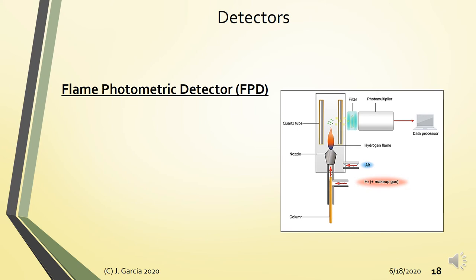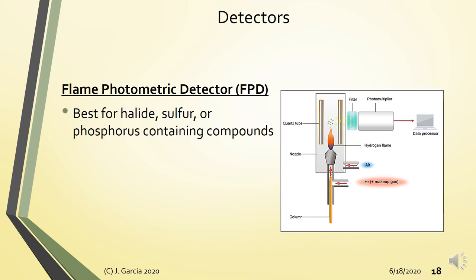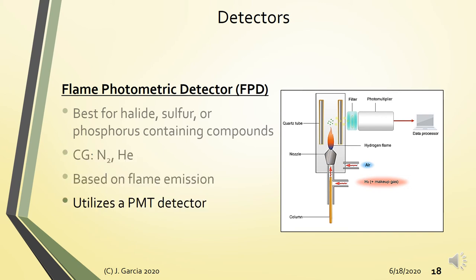The flame photometric detector (FPD) is used for halide-, sulfur-, or phosphorus-containing compounds. It is based on light emission: compounds containing halide, sulfur, or phosphorus emit characteristic emissions during combustion. Common carrier gases are nitrogen and helium. It utilizes a photomultiplier tube and is quite sensitive as a detector.